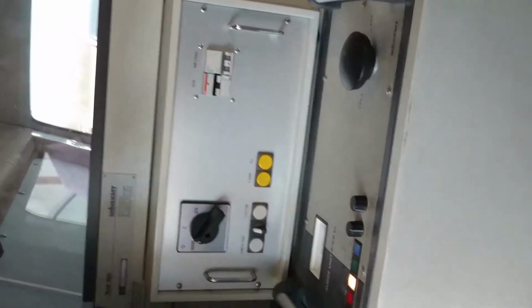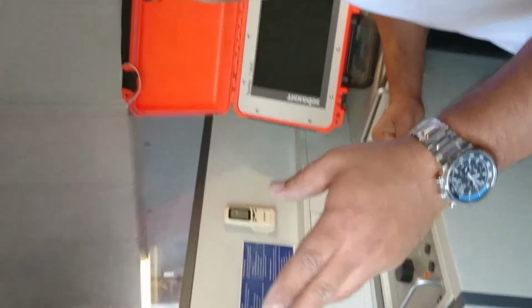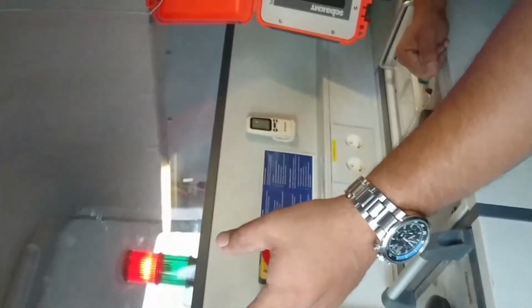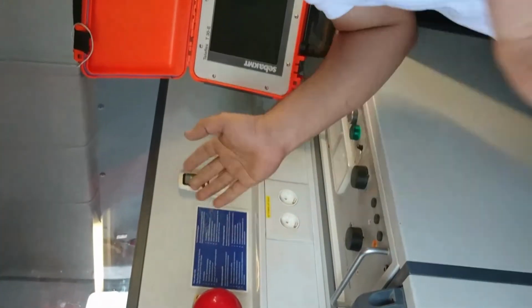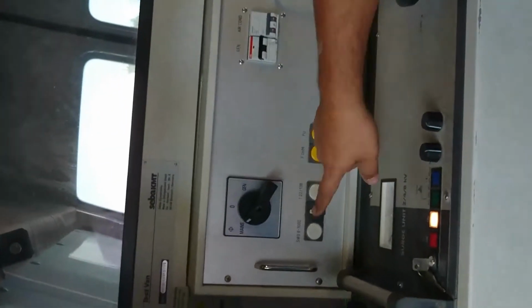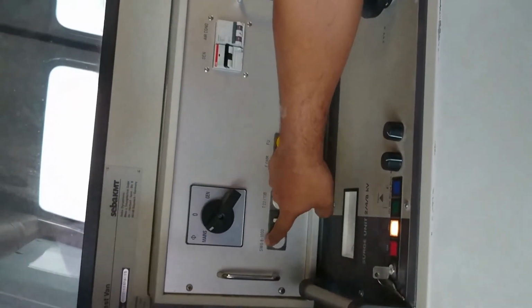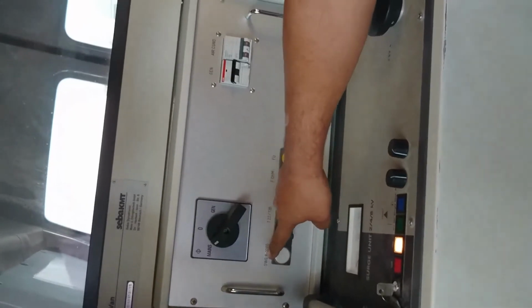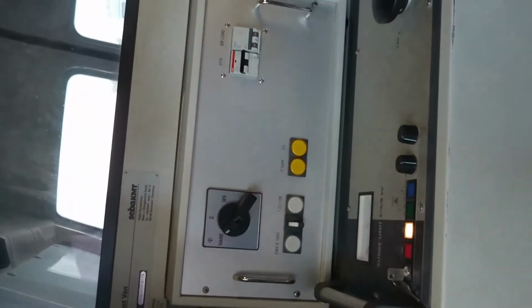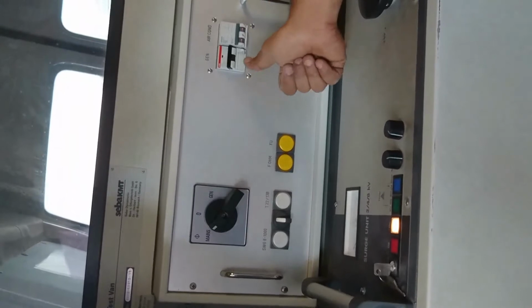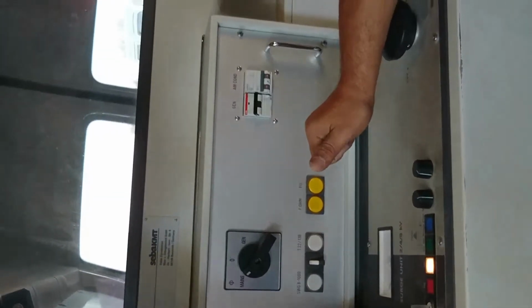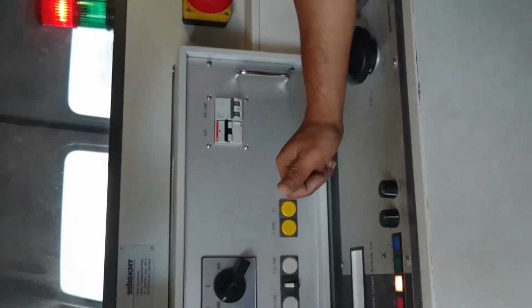So what we start now, we said we will test this cable, either it's healthy or it's faulty. So the connection is already done, so we can go up to switching, we can do the surge, and we can do the high voltage resistance. So we do the high voltage resistance.